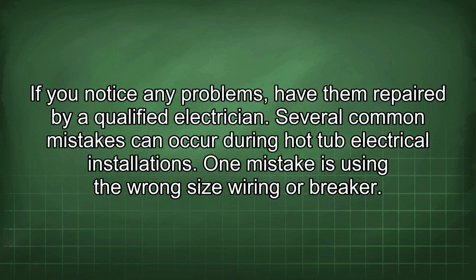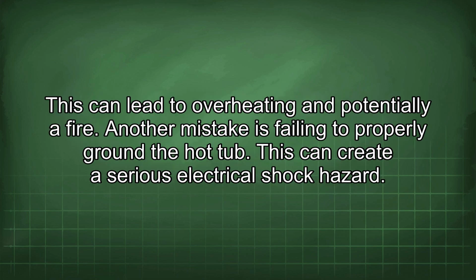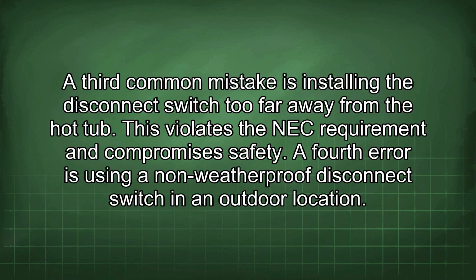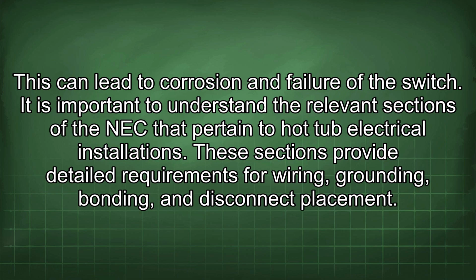Several common mistakes can occur during hot tub electrical installations. One mistake is using the wrong size wiring or breaker. This can lead to overheating and potentially a fire. Another mistake is failing to properly ground the hot tub. This can create a serious electrical shock hazard. A third common mistake is installing the disconnect switch too far away from the hot tub. This violates the NEC requirement and compromises safety. A fourth error is using a non-weatherproof disconnect switch in an outdoor location. This can lead to corrosion and failure of the switch.